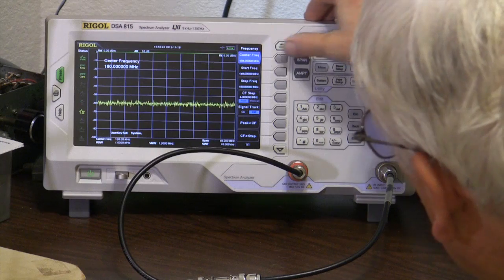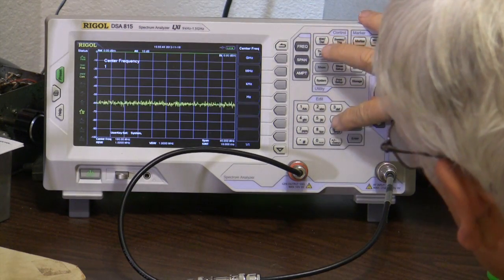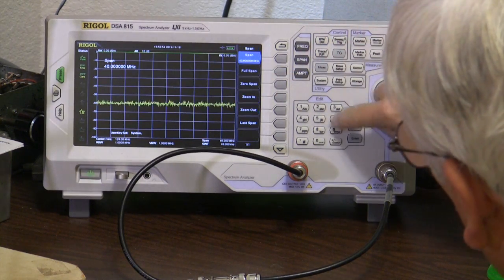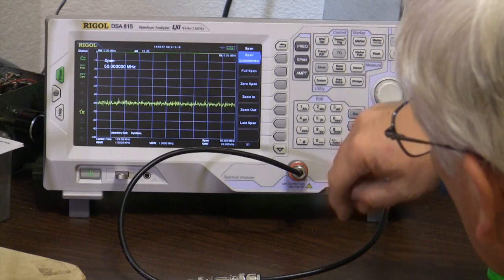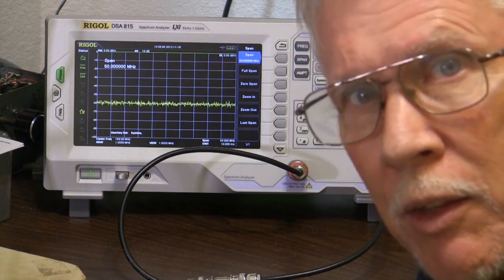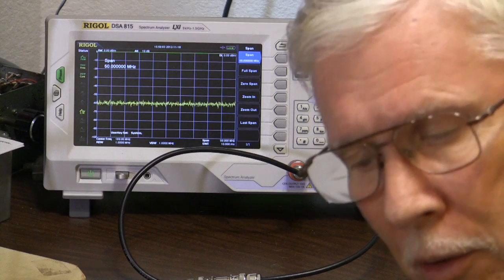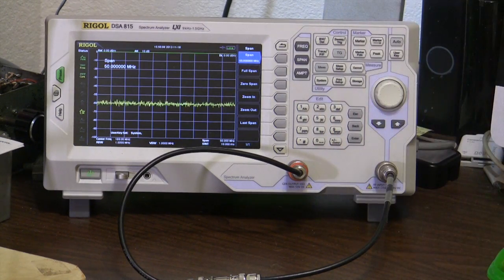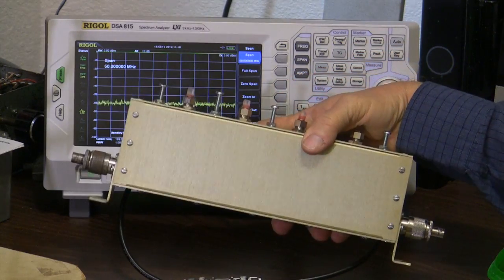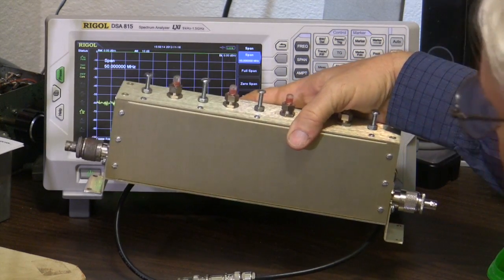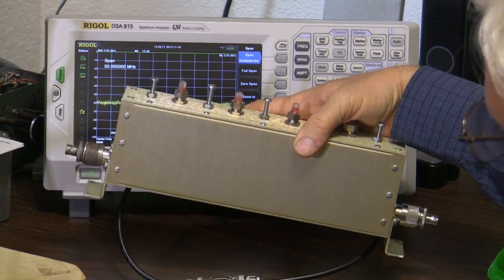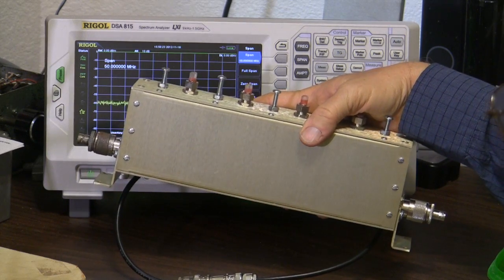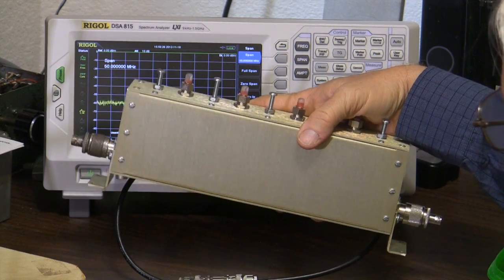They had it centered at 169. They had a span of 50 megahertz. So we'll do the same thing. So 169 frequency, center frequency, 169 megahertz. And then we'll do a span of 50 megahertz. So now we have exactly the same thing that they had when they did their evaluation of this unit. Now, this thing has been kicking around for a while. It's actually 2004 or something like that that this was made.